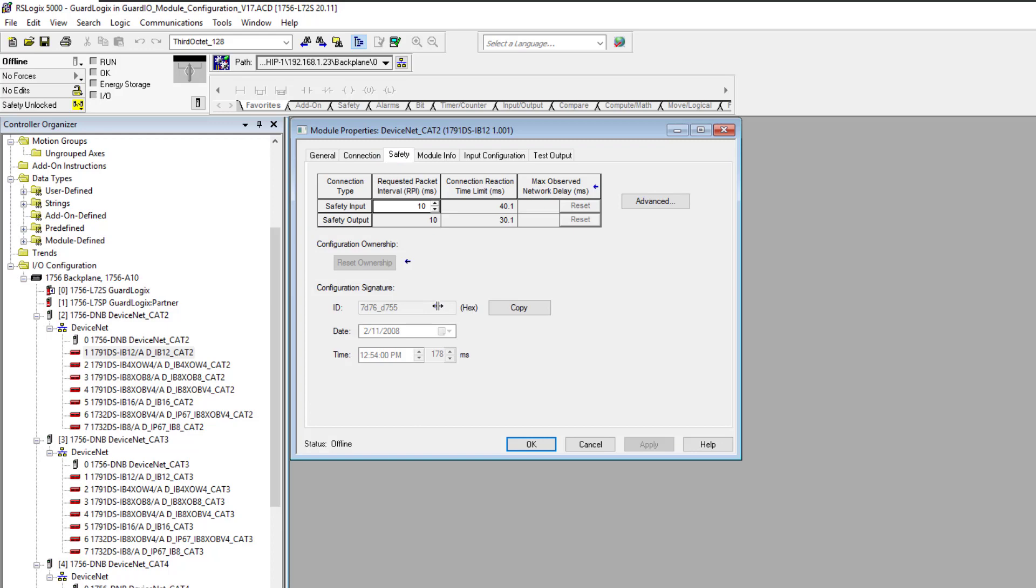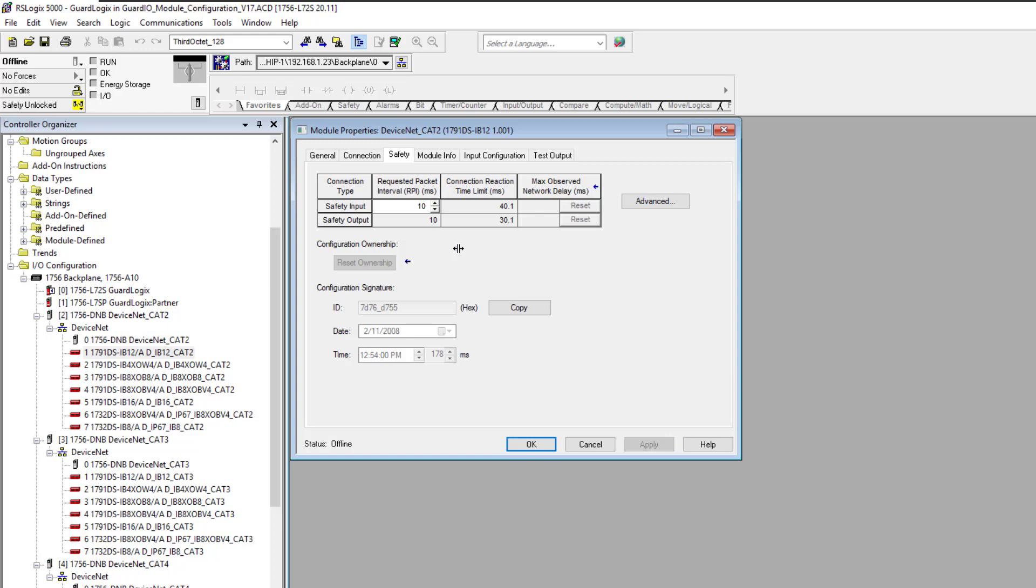So when you replace an IO card or an IO device, could it be remote IO, local IO, whatever the case may be, if it's owned by the safety processor, you're going to have to go into the IO, then go to the safety tab, and then reset the ownership to the processor. It's very important you do that because it will not actually accept that new component without ownership, because it is a safety protocol.